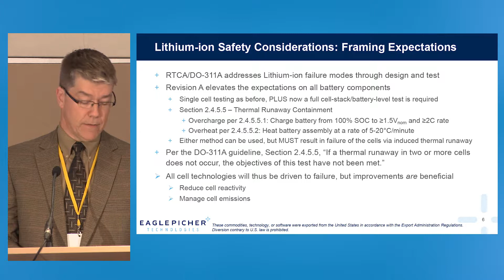With the battery management system, it's understood that a BMS is required to mitigate against abusive cell conditions, and protect against external short circuit that could lead to cell venting, overcharge or overvoltage, which can plate lithium from the matrix cathode onto the anode, overcurrents or overrate, which degrades the separator material and results in plating of lithium, undervoltage or over-discharge, where we actually pull oxide coppers from the substrates of the anode onto the cathode material.